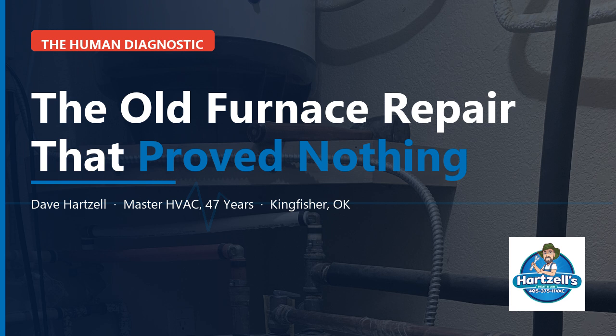Okay, what else? Dave mentions it wasn't overfired, which prevents something called short cycling. I've heard that term, but what is short cycling actually doing to the machine? Short cycling happens when a furnace is too large for the square footage of the house. It blasts a massive amount of heat, warms the house up in like 5 minutes, and shuts off. Then 10 minutes later, it turns on and blasts heat again.